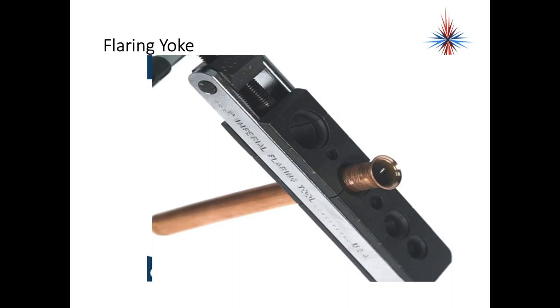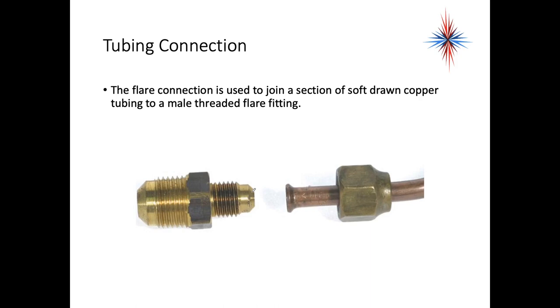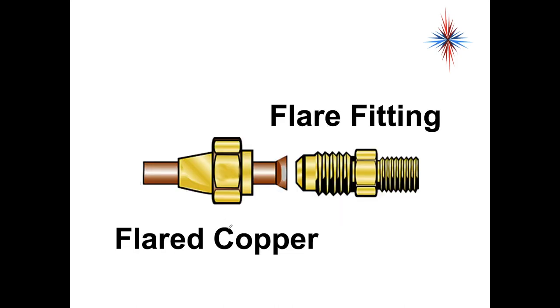The flare connection is used to join a section of soft drawn copper tubing to a male threaded flare fitting. When you look at this, you see that the beveled end of this fitting exactly matches the bevel of this flare. That's why it's really important to get this correctly into the flare block and don't do it in an angle—it has to be a straight line.